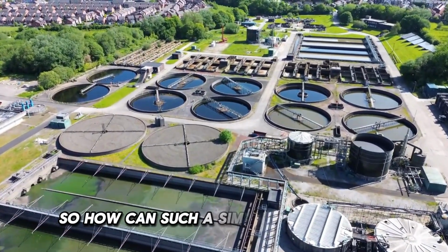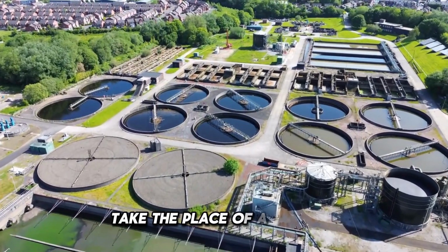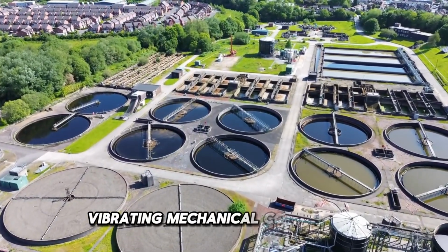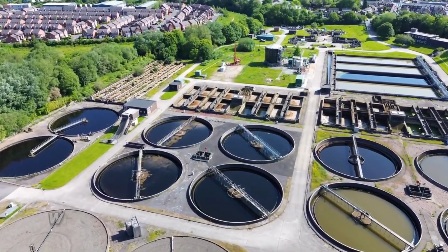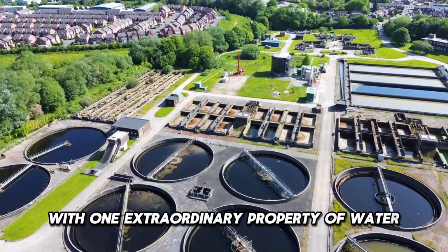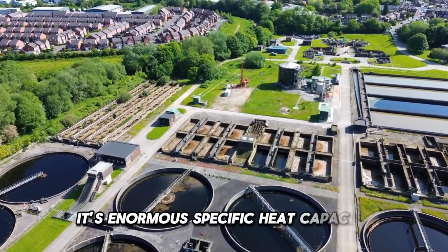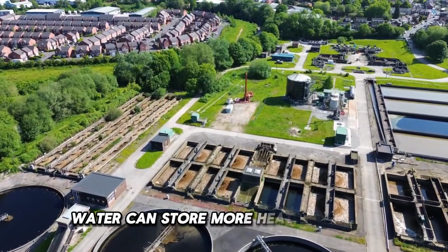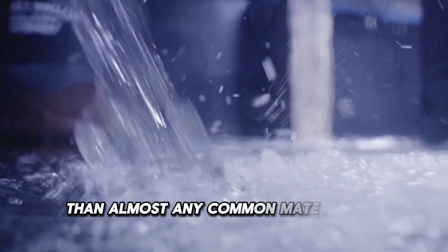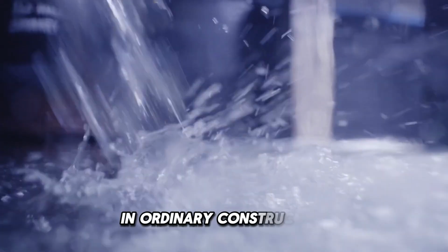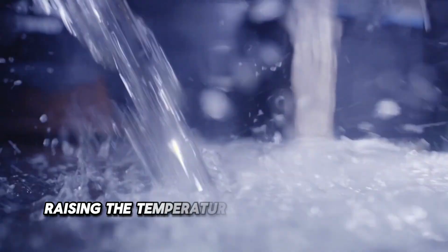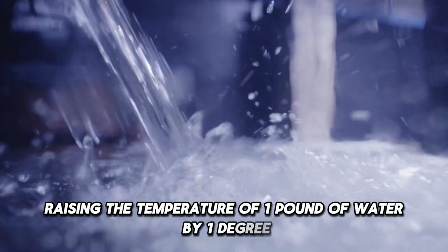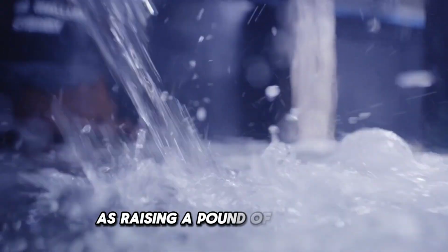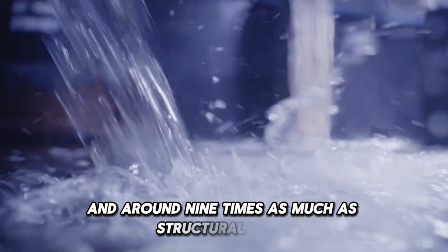So how can such a simple plumbing loop take the place of a roaring, vibrating mechanical compressor? The answer begins with one extraordinary property of water: its enormous specific heat capacity. Water can store more heat per pound than almost any common material we encounter in ordinary construction. Raising the temperature of one pound of water by one degree requires roughly four times as much energy as raising a pound of aluminum by the same amount.